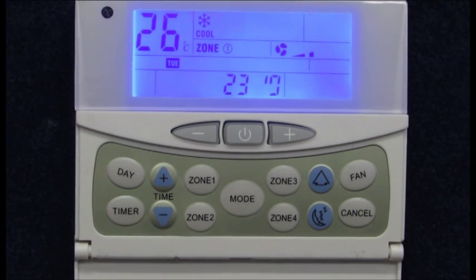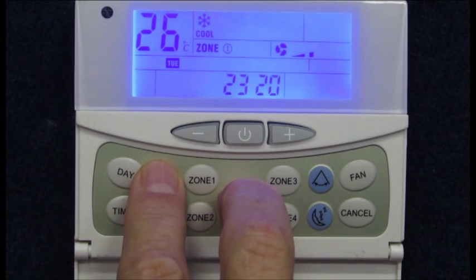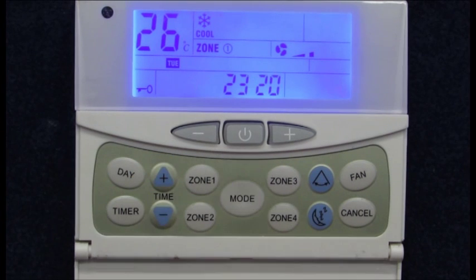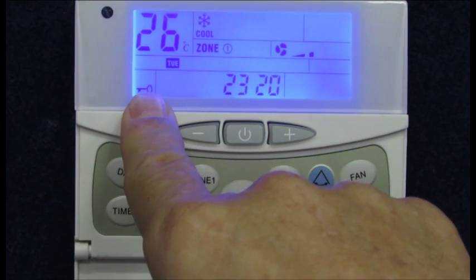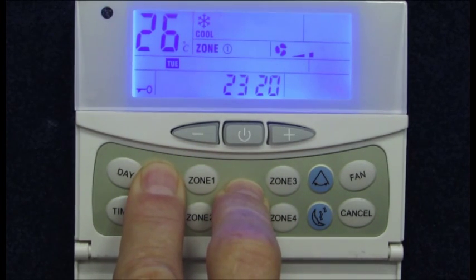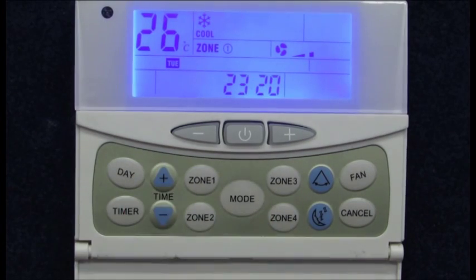If you want to stop people tampering with the settings, then you can apply the key lock function. This is activated by holding down the time plus and mode buttons together for three seconds, and you will see a key displayed indicating the controller is locked. Use the same buttons to unlock. So that's the time plus and mode buttons. Once locked, only the on-off button and the after-hours bypass function previously mentioned can be operated.